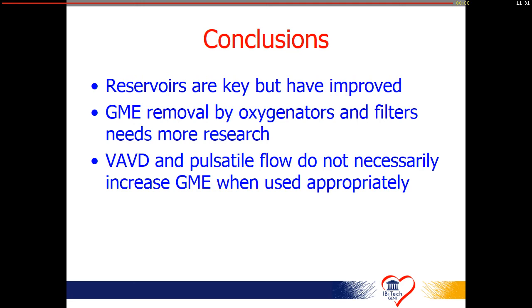I think there is a misunderstanding. I didn't say that they are as good. What I said is that the working principle is different. In a depth filter, it can only work at very low velocities. That's the only way it can work. And then you can discuss how many layers you put in there, but the basic principle is it has to be at low velocity.